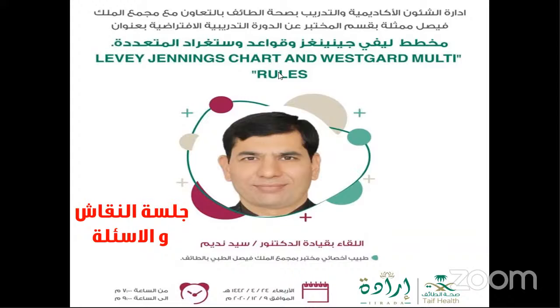So, Mr. Muhammad Qasim, I will repeat once again the difference between quality control and calibrators. The quality control does not have a fixed value. It has a variable result, whereas a calibrator has a fixed value. The quality control material is processed based on the calibrator.